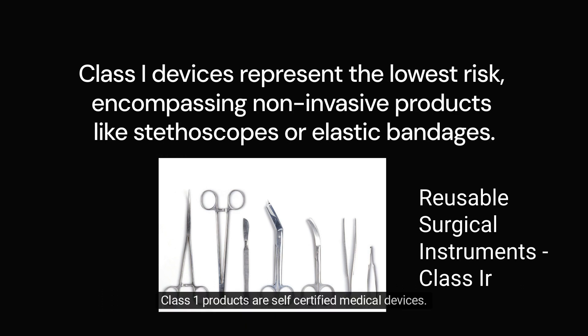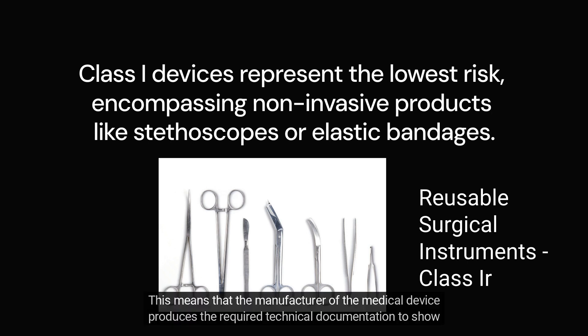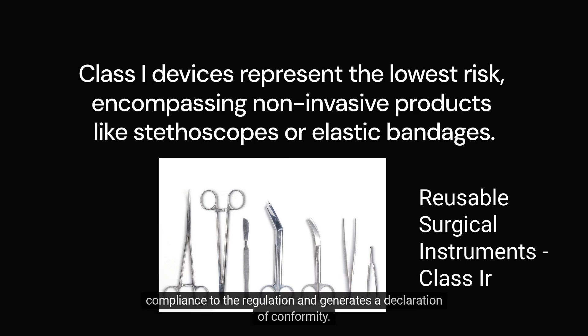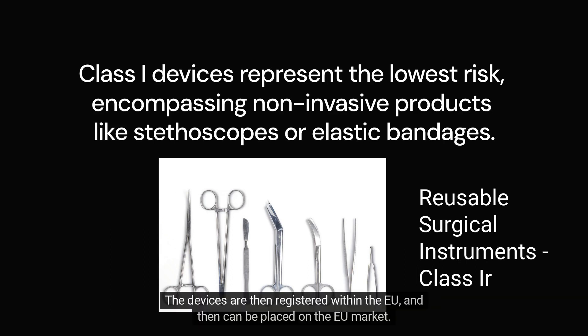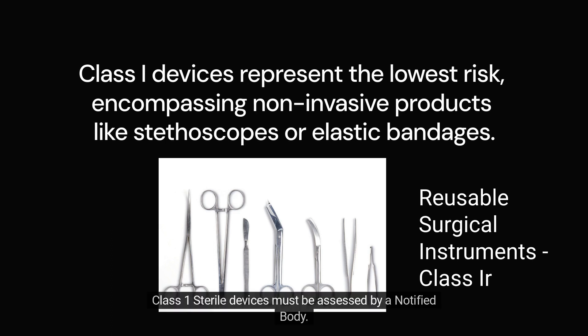Class 1 products are self-certified medical devices. This means that the manufacturer produces the required technical documentation to show compliance to the regulation and generates a declaration of conformity. The devices are then registered within the EU and can be placed on the EU market.